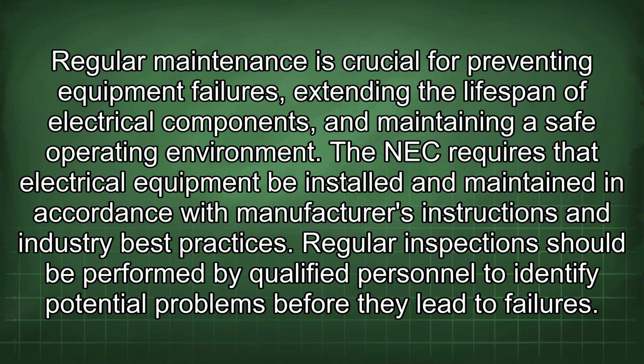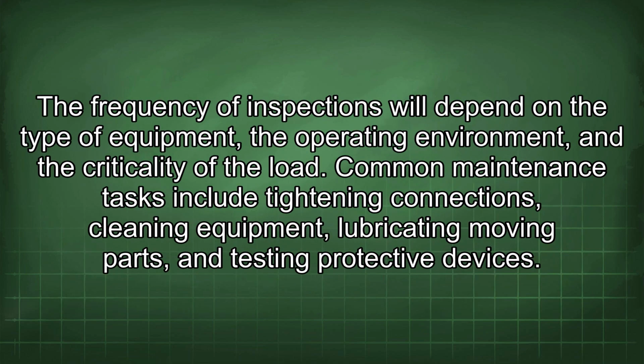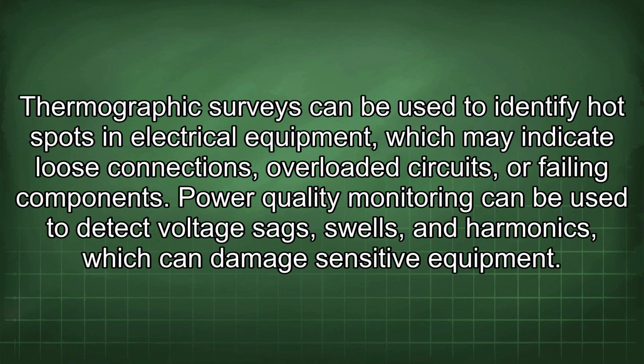The NEC requires that electrical equipment be installed and maintained in accordance with manufacturer's instructions and industry best practices. Regular inspections should be performed by qualified personnel to identify potential problems before they lead to failures. The frequency of inspections will depend on the type of equipment, the operating environment, and the criticality of the load. Common maintenance tasks include tightening connections, cleaning equipment, lubricating moving parts, and testing protective devices. Thermographic surveys can be used to identify hot spots in electrical equipment, which may indicate loose connections, overloaded circuits, or failing components. Power quality monitoring can be used to detect voltage sags, swells, and harmonics, which can damage sensitive equipment.